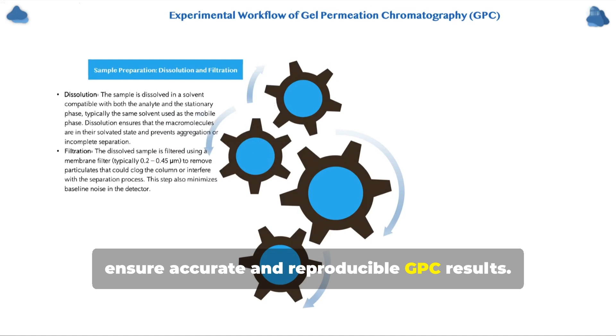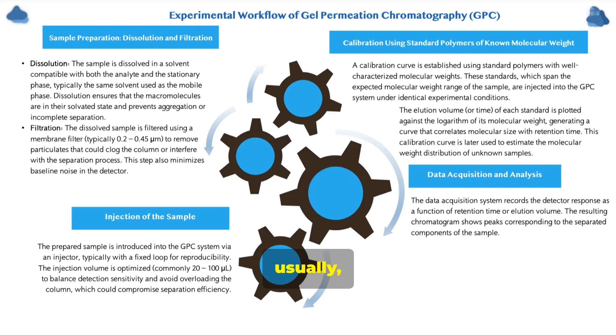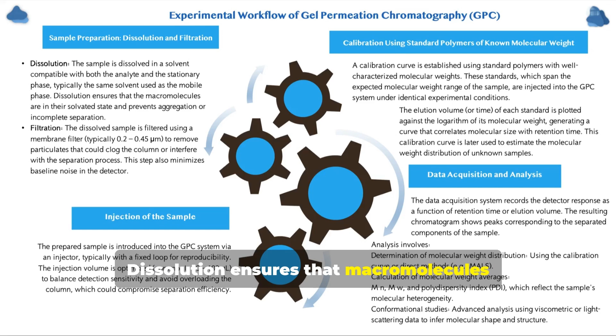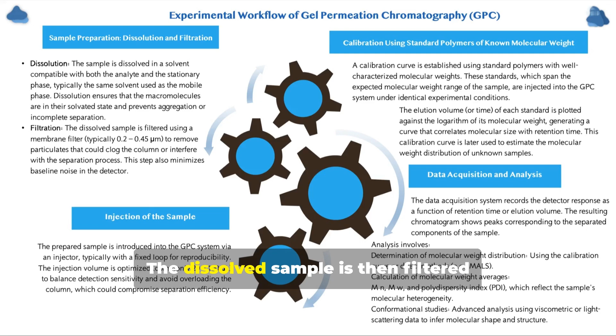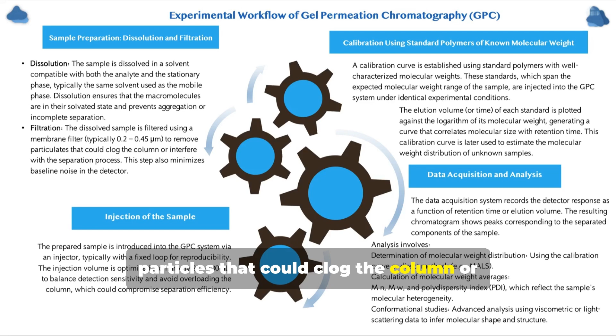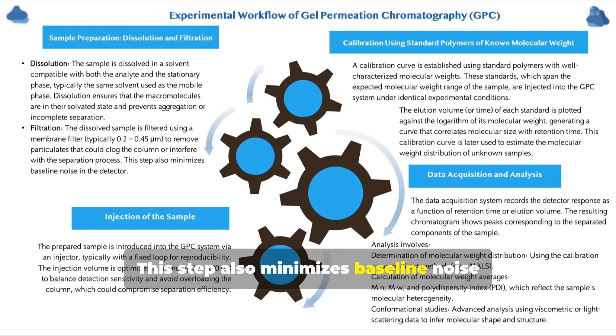Proper sample preparation is essential to ensure accurate and reproducible GPC results. The sample is dissolved in a solvent compatible with the analyte and stationary phase, usually the same solvent used for the mobile phase. Dissolution ensures that macromolecules are in a solvated state and prevents aggregation or incomplete separation. The dissolved sample is then filtered using a membrane filter to remove particles that could clog the column or interfere with the separation process. This step also minimizes baseline noise in the detector.